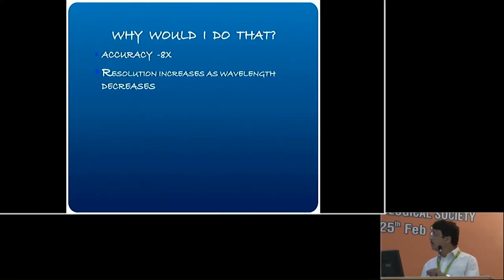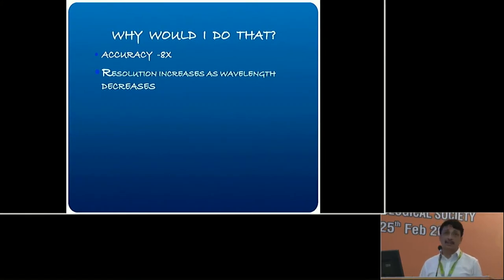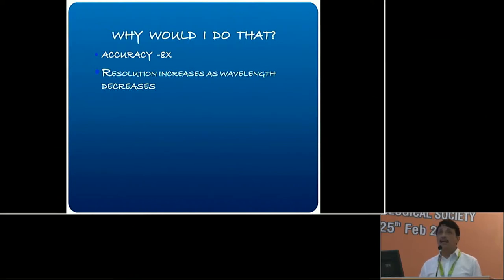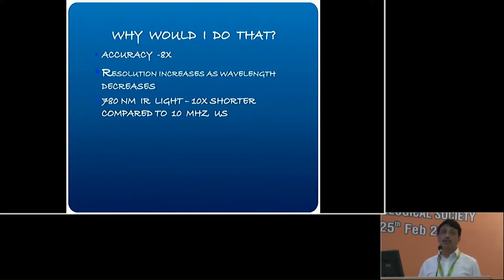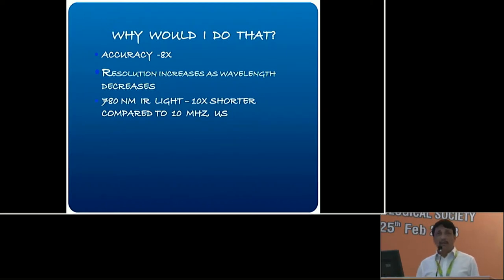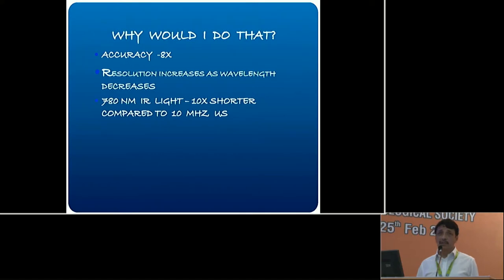Why is that? Resolution increases as wavelength decreases — basic principles of physics. Infrared light at about 780 nanometers wavelength is about 10 times shorter than that of a 10 megahertz ultrasonic probe. The wavelength is shorter, so resolution increases and accuracy increases. That is one particular reason why I should switch to optical biometry.